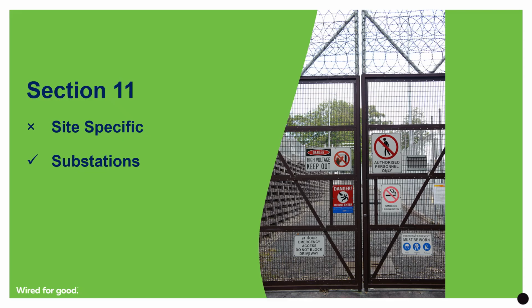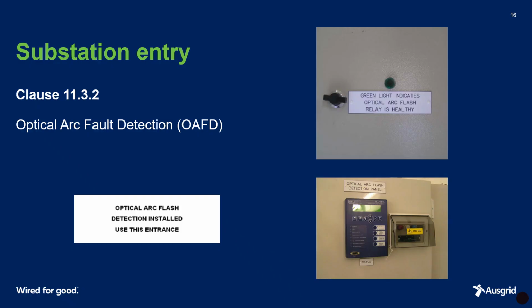The title and content of Chapter 11 have been changed from site-specific to substations. Clause 11.3.2 sets out the controls required for access to substations that are fitted with optical arc fault detection protection schemes.